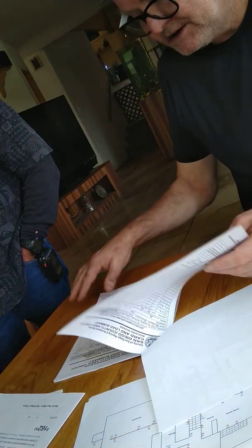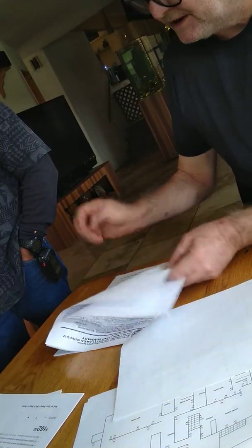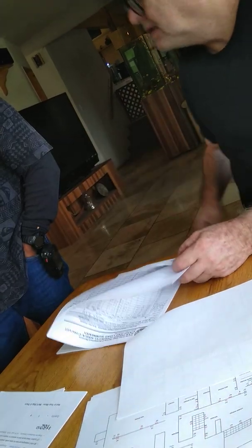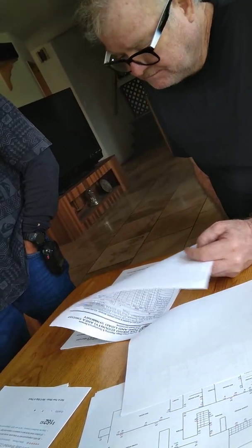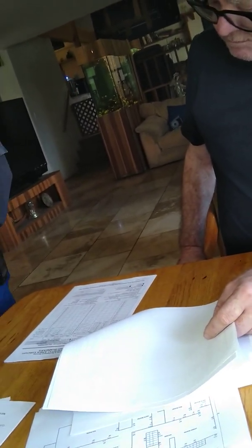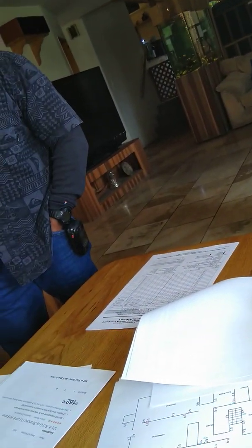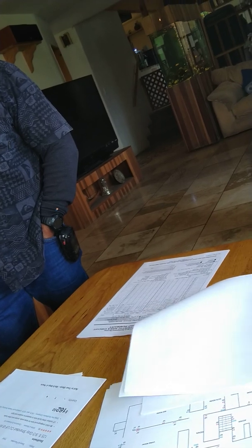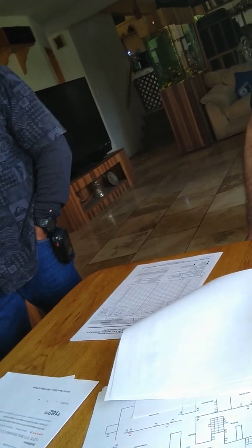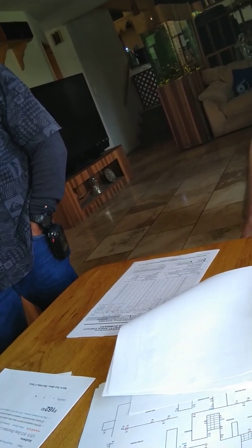Circuit breaker box by circuit breaker box. If I could break into your thoughts now, Mike. On the sub panels, what size feeder is each one being fed from? So let's say you have a couple of sub panels, right? Yeah, there are 8 gauge wire going to each sub panel.